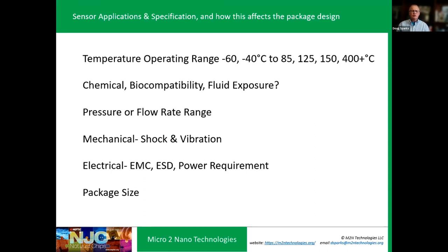For many sensors, you've got to think of chemical exposure. Is it a chemical sensor, or is it in an environment where it will be exposed to a chemical, like a flow sensor or pressure sensor? It's not a chemical sensor, but it's going to be in a fluid. For medical devices, it may have to be biocompatible, so you've got to think of all those issues with material compatibility with your package housing.